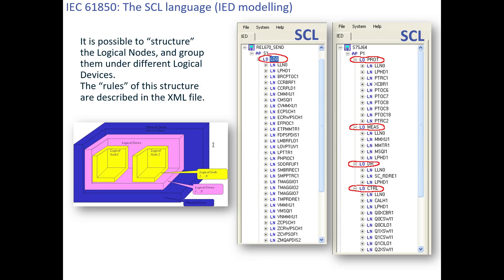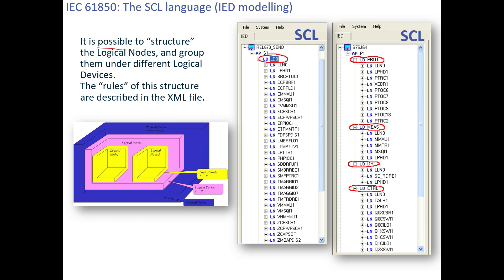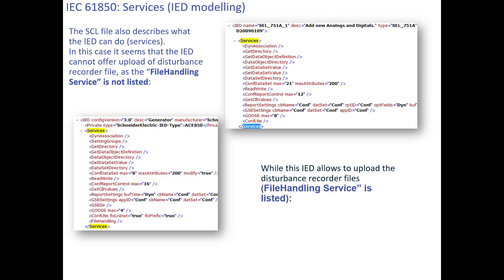The same structure applies: physical device (REL670, 7SA522, or P444) → many logical devices → one logical device LD0 → many logical nodes such as PDIS, PTOC, PIOC → data objects → data attributes. It is possible to structure logical nodes and group them under different logical devices. The rules of this structure are described in the XML file.